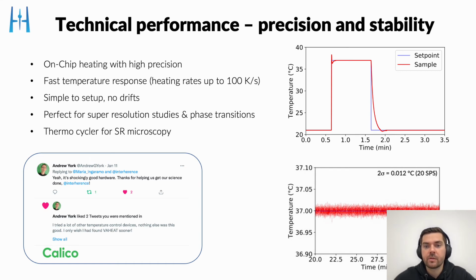The fast thermal response is shown here. The blue is the set point and the red curve is the actual sample temperature. You can then program arbitrary temperature profiles, and the sample volume follows accordingly. With that, you can achieve temperature changes of up to 100 Kelvin per second. And well, the precision and the simple ease of use is actually what people appreciate about the system.